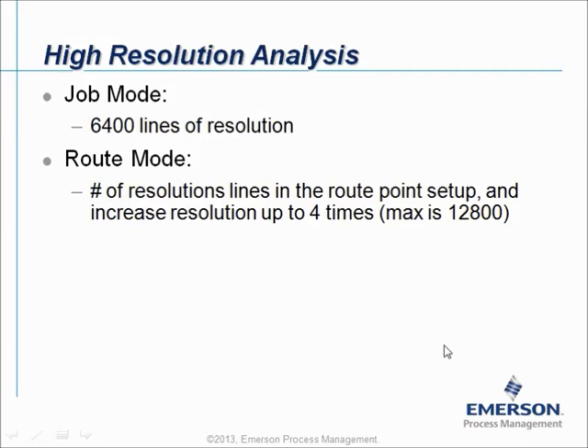You can collect high resolution data in the job mode or in the route mode. If you collect data in the job mode, the data will always be measured with 6400 lines of resolution. In the route mode it's a little bit different — the software will look into the point definition setup, take the number of resolution lines from your point setup, and increase them up to 4 times, with a maximum of 12800.